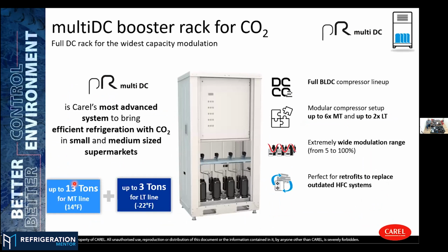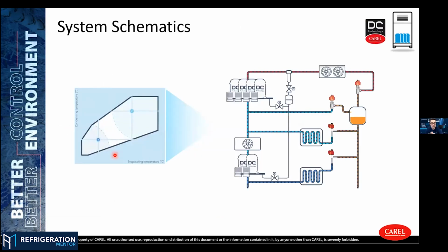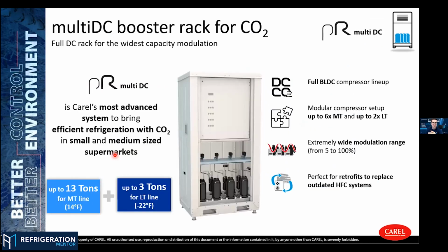And last but not least, these compressors are also available to manage in a booster application or in a rack application. We can manage up to 6 compressors for MT plus 2 compressors for LT, and we can make a much higher capacity in a small footprint. As you can see, this sample unit has about 4 foot by 4 foot of area. So it's a small footprint, and you can have a higher capacity solution with multiple compressors. So for that system, your size there would be 13 tons medium temp and 3 tons low temp in that one multi-DC booster rack. Is that correct? Yeah, you can sum up both capacities.